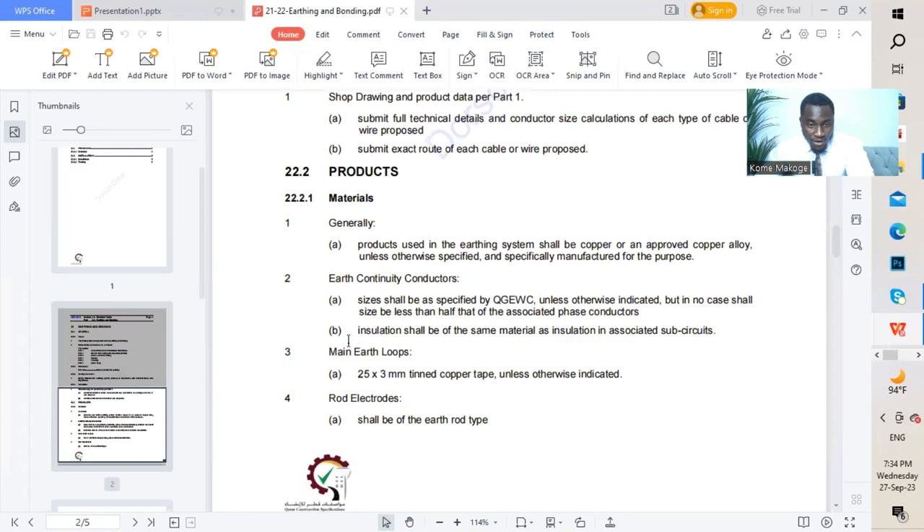Insulation shall be of the same material as insulation in associated sub-circuits — so all circuits will have the same insulation material. Moving to the main earth loop: we'll be using 25×3 mm tinned copper tape unless otherwise indicated.